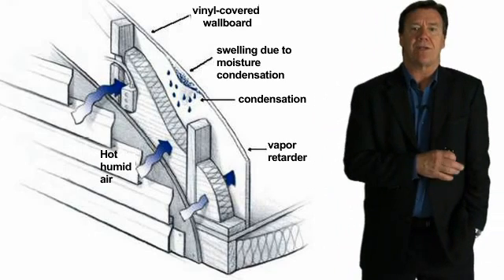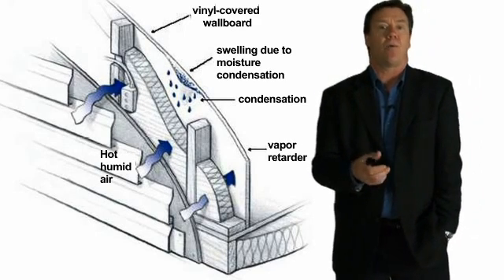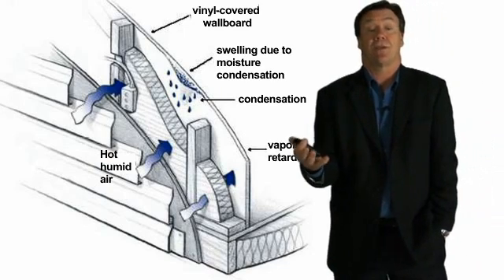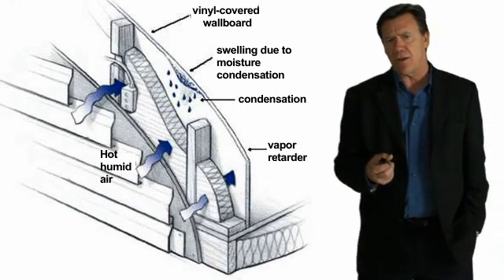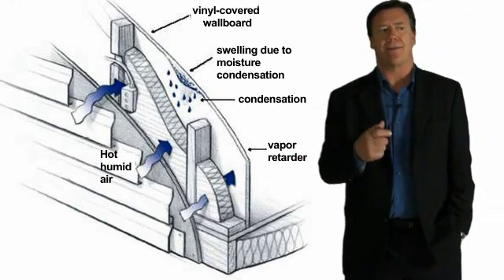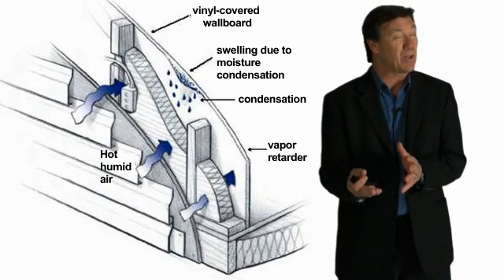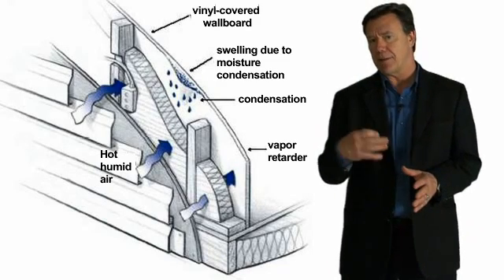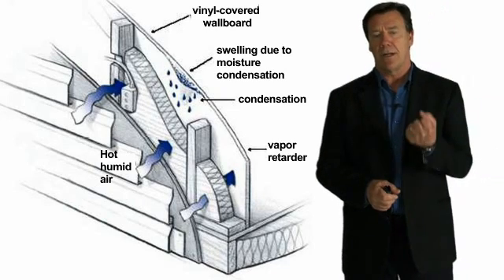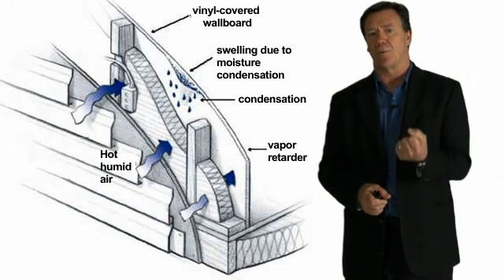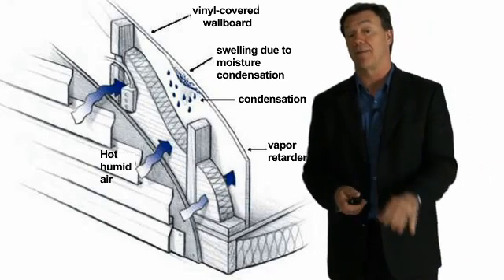Here's an example: if warm moist air infiltrates through the wall system and hits the back of the drywall, and the home is being cooled in the summer months, you can actually get condensation. That's another reason why the building codes have lightened up a bit on the vapor retarder requirements in hot and humid climates — because you don't want that vapor retarder to be a place where moisture can condense if the home is under a negative pressure.